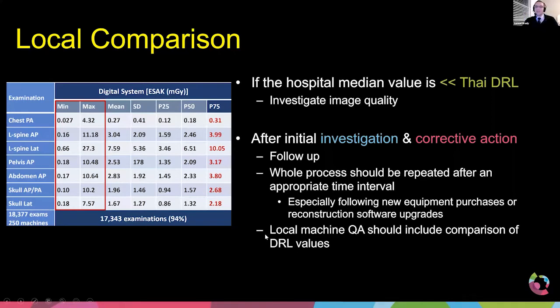And then one of the things that the ICRP 135 report recommends is that you obviously establish a QA process, a quality assurance process. So people like medical physicists will come in and do annual or some type of testing, be it quarterly, semi-annual, or annual testing. They may work in conjunction with technologists, but you have a group or a team that establishes a quality assurance program. And as they go through this program, they're going to be testing various things: machine output, spatial resolution, is there proper contrast in the image? They have their list of things they're testing.